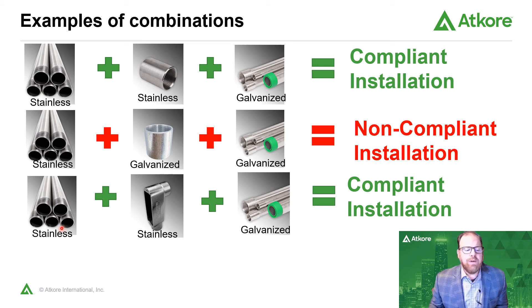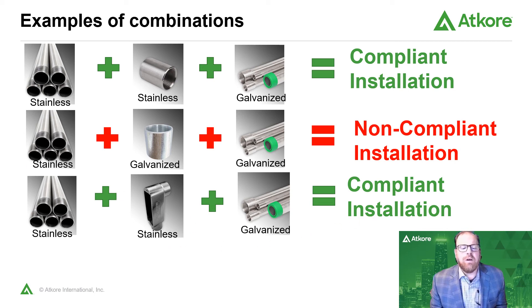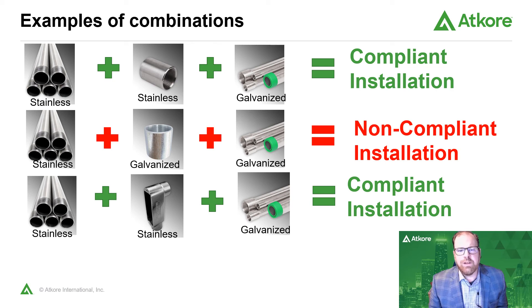Looking at a third example: stainless steel conduit, a stainless steel conduit body, and then galvanized rigid conduit — this is a compliant installation. You could use a stainless steel conduit body, or swap it out for a compression fitting, set screw fitting, or any stainless steel fitting. Any of those installations will be compliant.